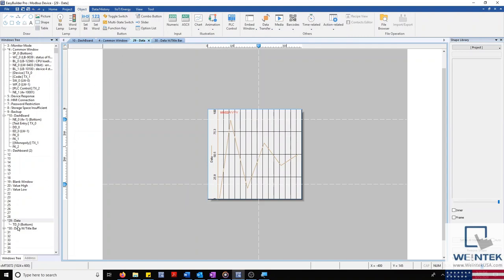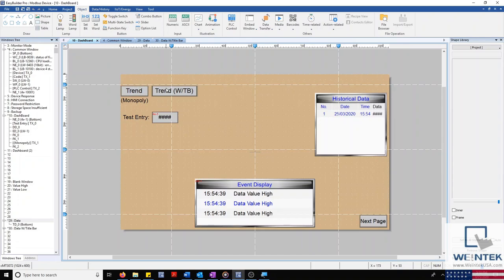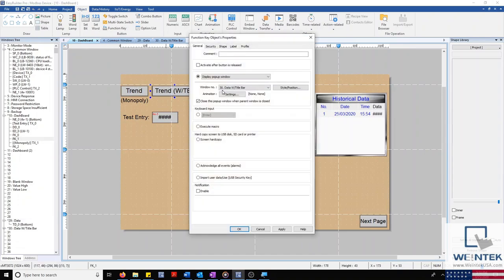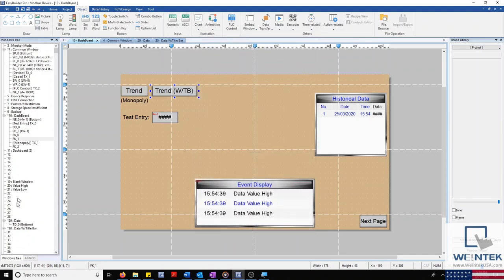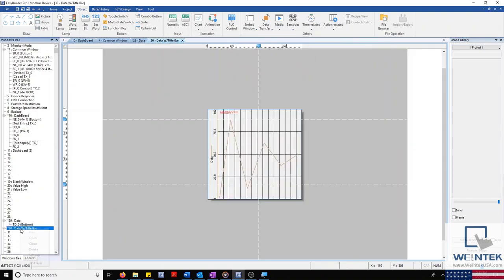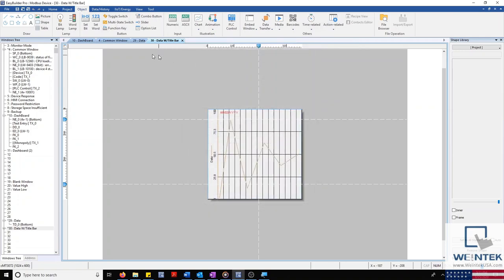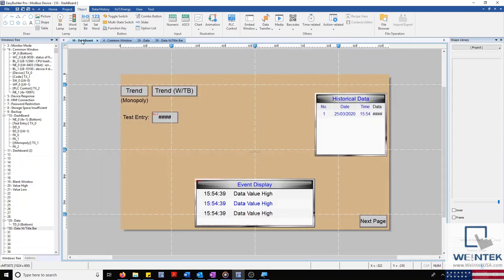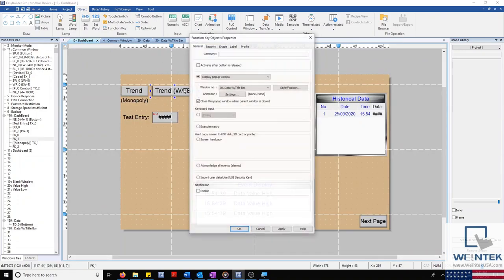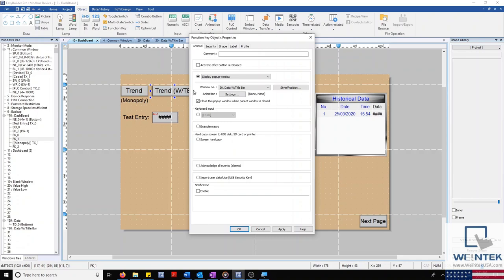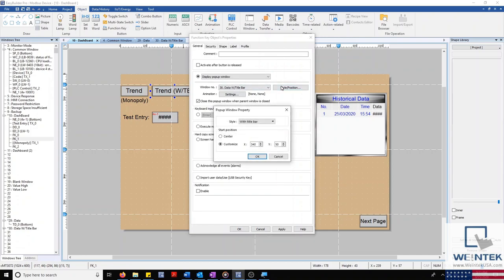Our second function key will display a similar window, with the exception that the window does not hold monopoly over the screen, and that this window has something called a title bar. A title bar will allow us to move the window around the screen using a mouse or our finger on the HMI. It can be configured within the function key itself by selecting style and position, and then selecting with title bar in the style tab.